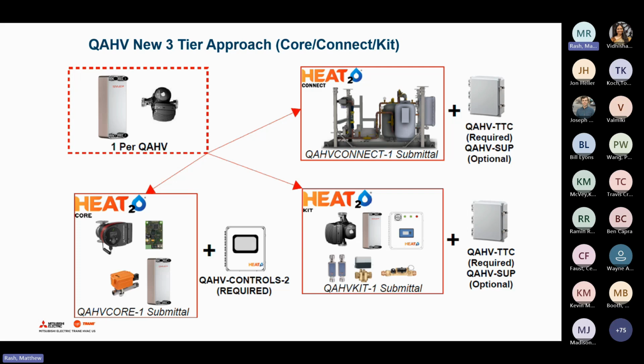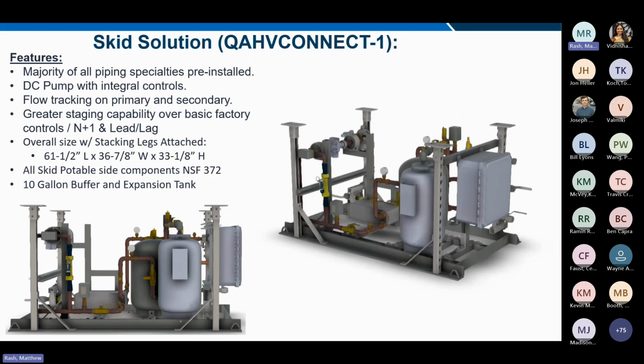They're specially designed with sparge fittings and strategic thermistor well locations. So again, with this three-tier offering that we've expanded, you've got basically these major categories that you're selecting. The QAHV units, the number are going to vary by project. The quantity of tanks are going to vary. The swing tank size will vary. Again, that's procured by others.